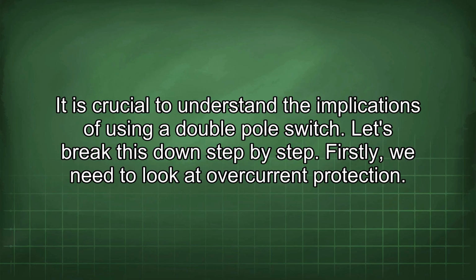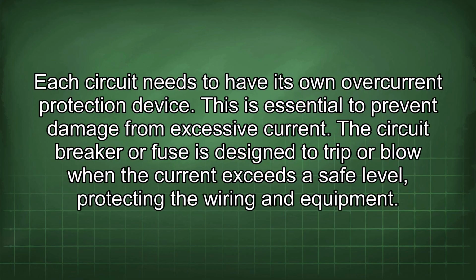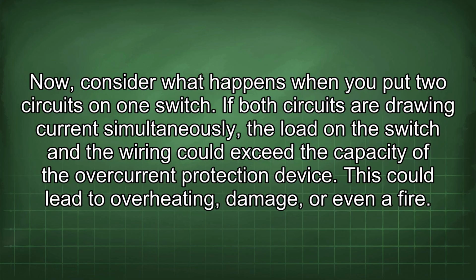It is crucial to understand the implications of using a double-pole switch. Let's break this down step by step. Firstly, we need to look at overcurrent protection. Each circuit needs to have its own overcurrent protection device. This is essential to prevent damage from excessive current. The circuit breaker or fuse is designed to trip or blow when the current exceeds a safe level, protecting the wiring and equipment. Now, consider what happens when you put two circuits on one switch.